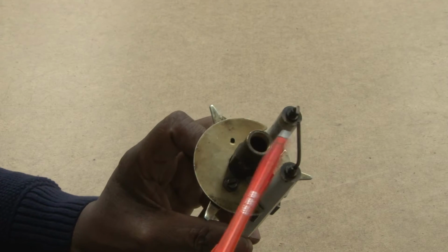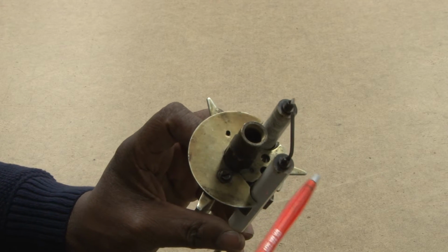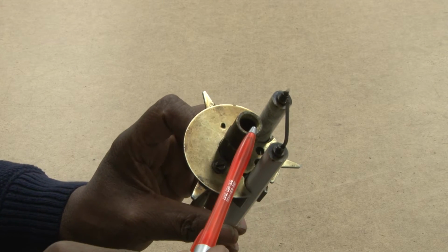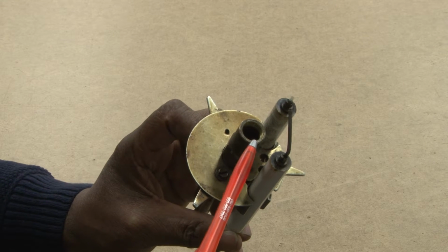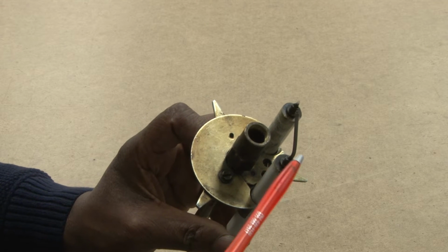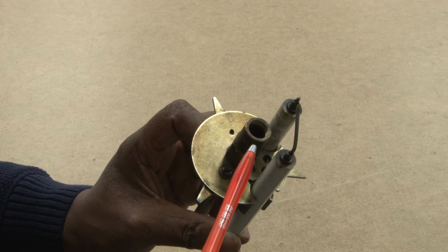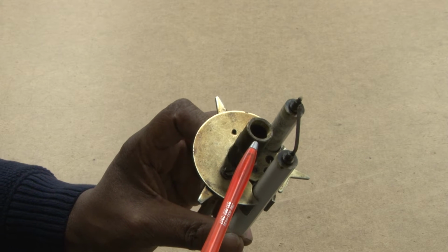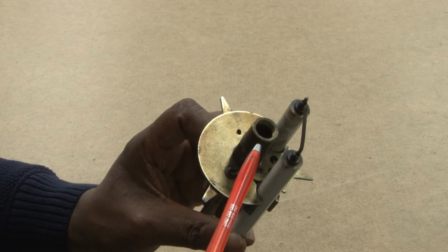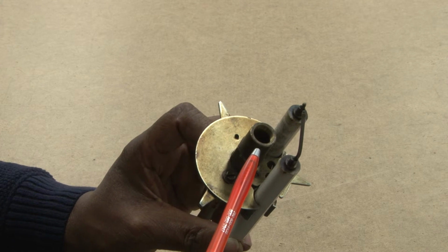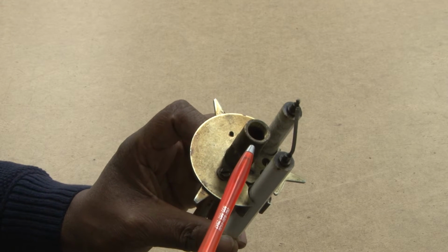And we see the oil burner. It will have a tube which has a port for a nozzle to be connected to it. This nozzle will be screwed into the threads, and it will cause the oil to be atomized into small particles so it can be ignited.